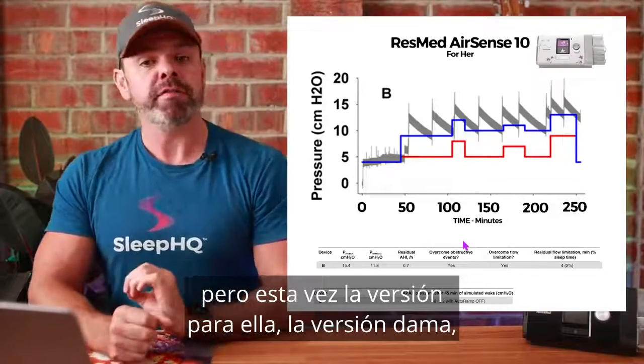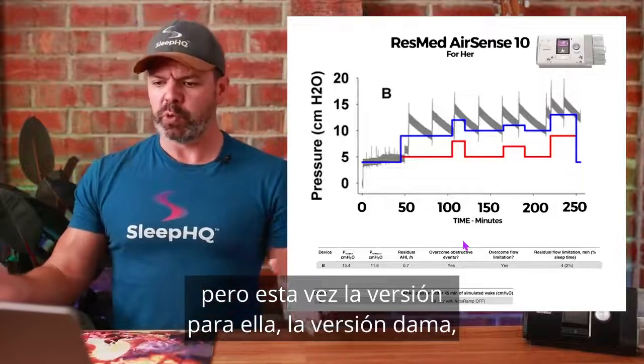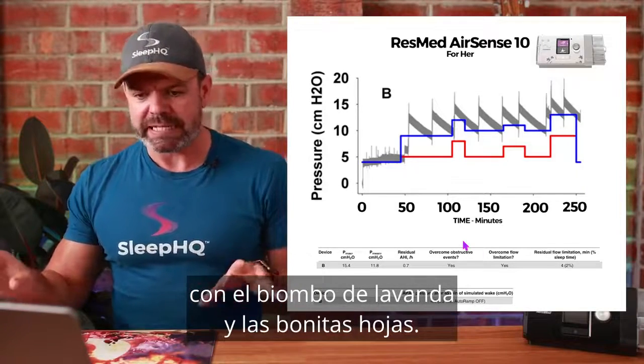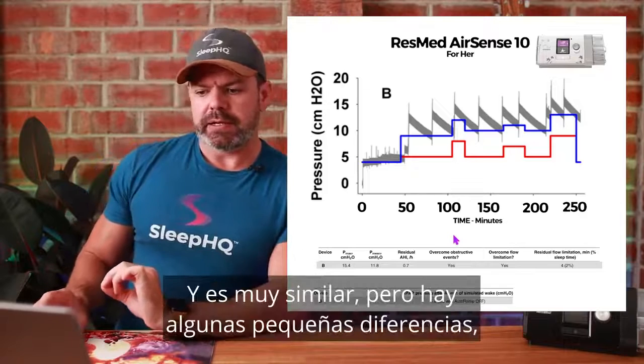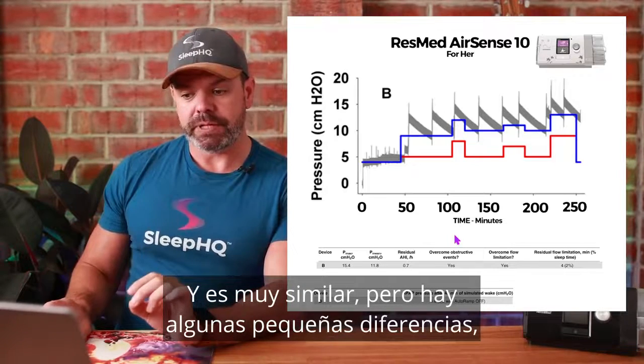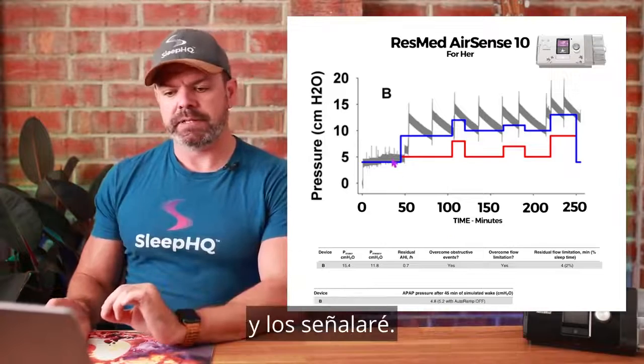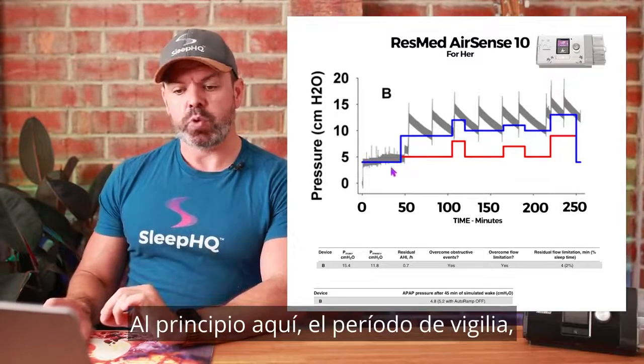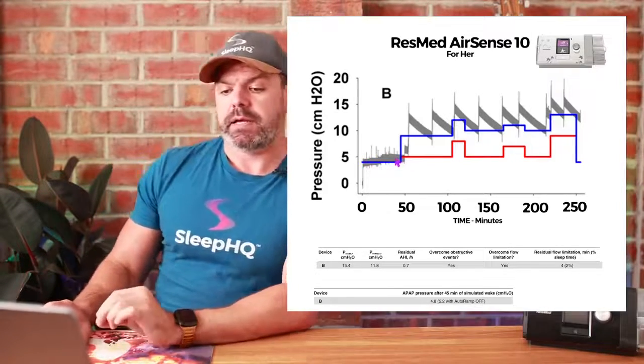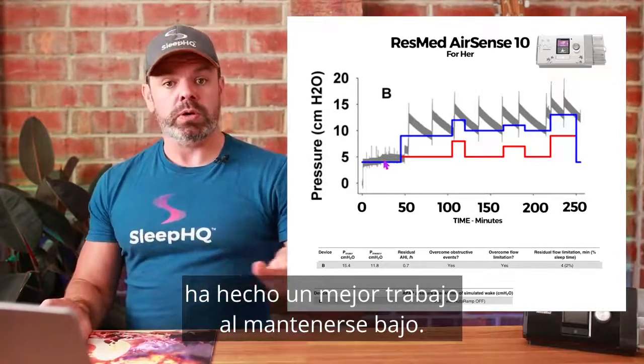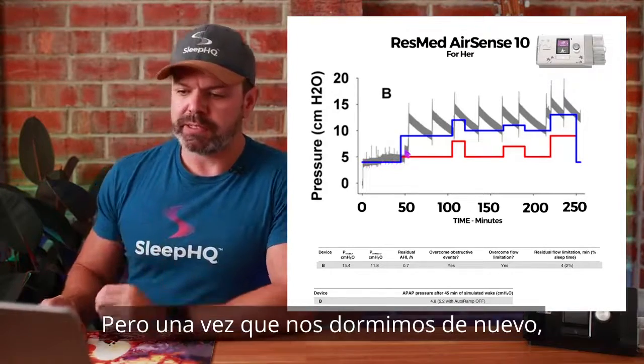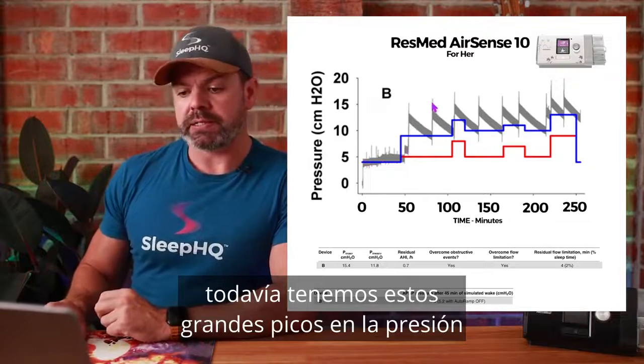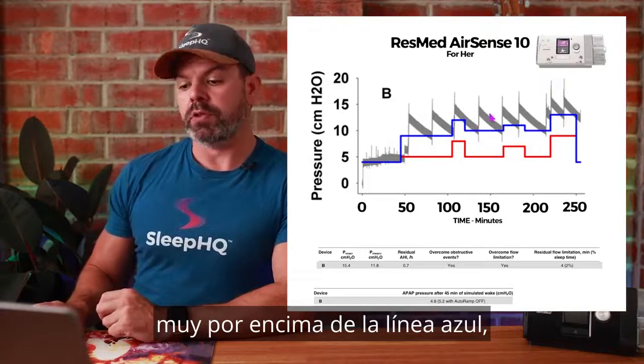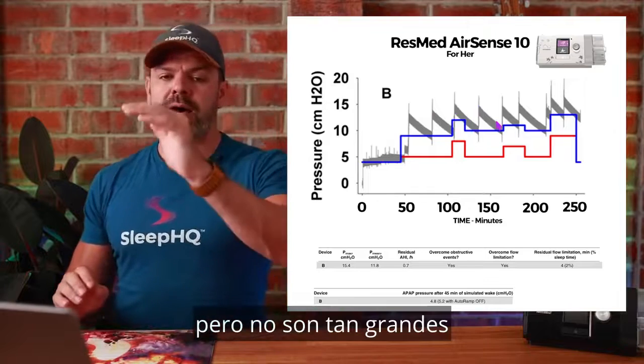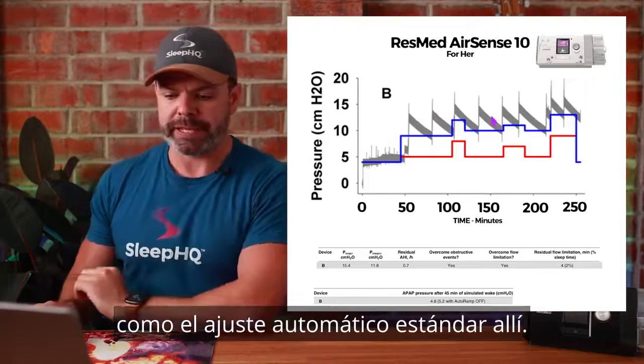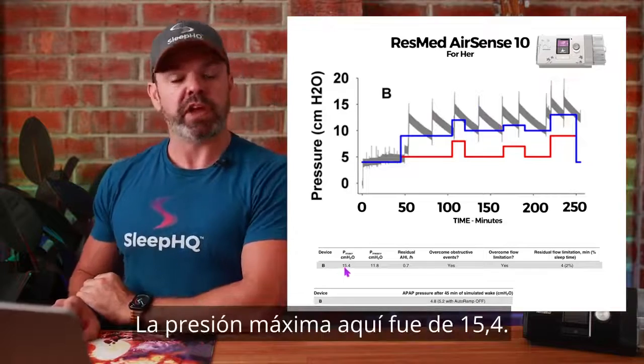All right, mates, moving on to the second bench test CPAP machine, and it's another AirSense 10, but this time the for her version, the lady version, with the lavender screen and the pretty leaves. And it's very similar, but there's a few small differences, and I'll point them out. In the beginning here, the wake period, it's done a better job at staying low. But once we fall asleep again, we still get these great big peaks in the pressure, well above the blue line, but they're not quite as large as the standard AutoSet there. Pressure max here was 15.4.